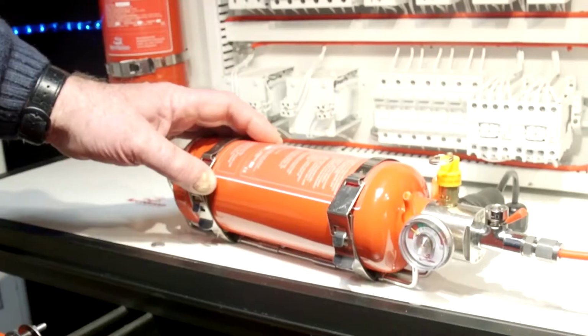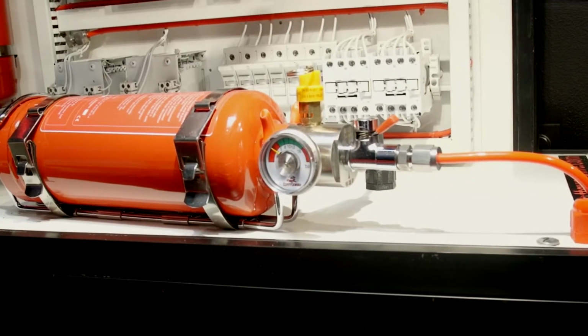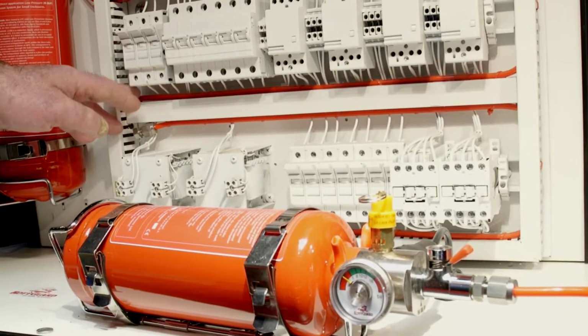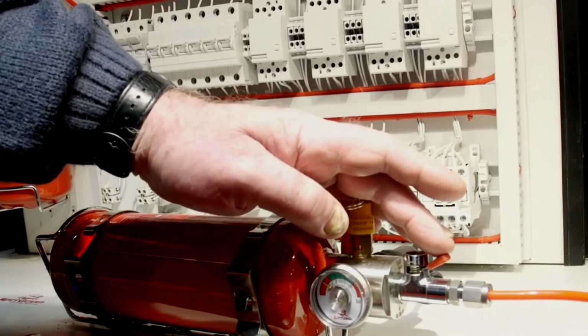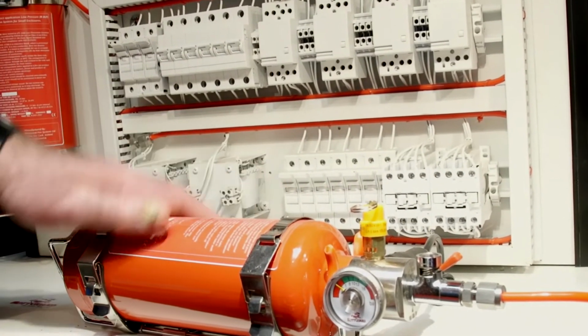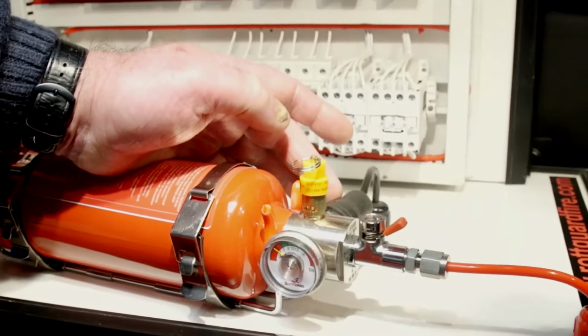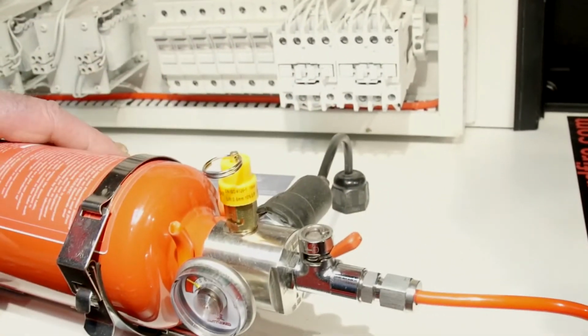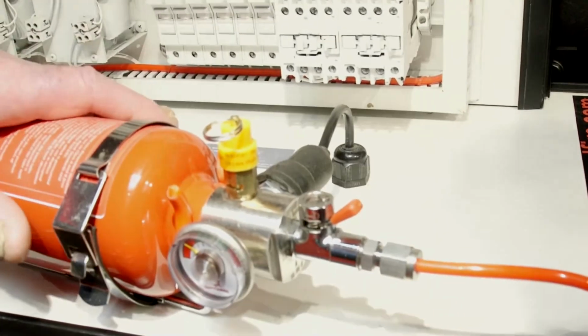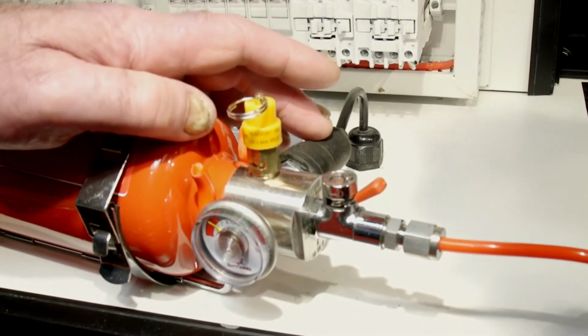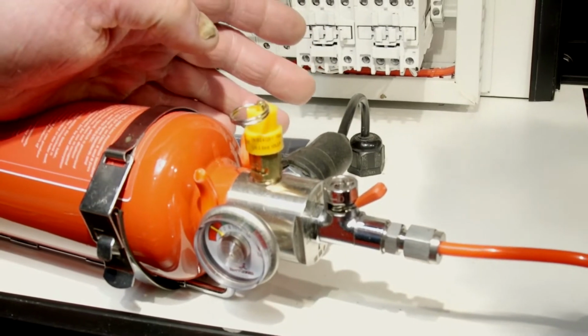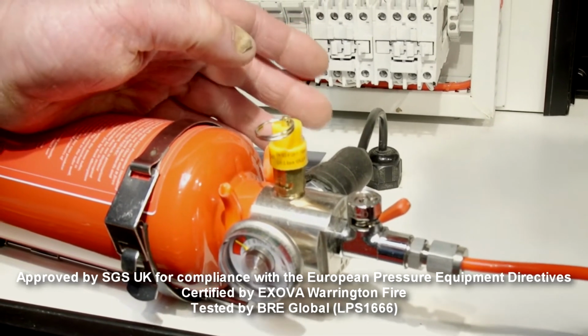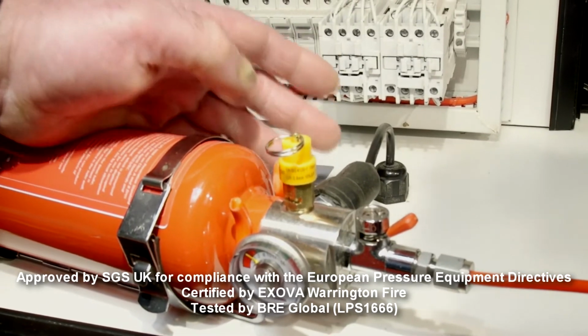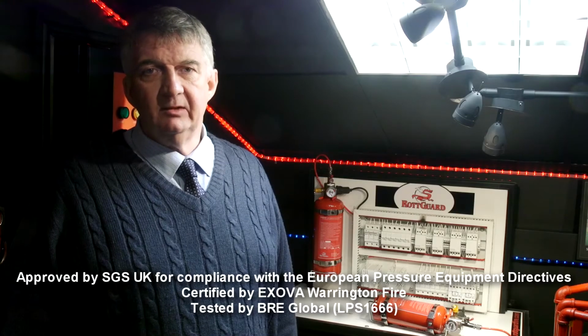We're showing here how the cylinders can be mounted vertically or horizontally. Once the tubing has been installed and pressure tested, the ball valve here is opened and that releases the liquefied agent through the tube. The pressure switch is normally open when the cylinder is pressurized, and on activation of the system, this pressure switch can signal to a fire alarm system, be it a conventional one or an addressable one's IO unit. The systems have been installed in over 20 countries across 5 continents.